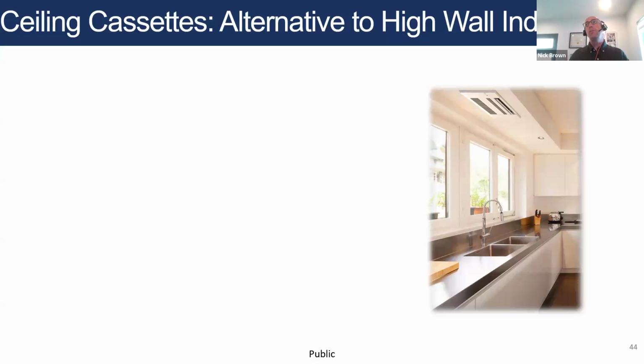Note that all these heat pumps are going to make condensate. So you need to locate the indoor unit, whether it's high wall or ceiling cassette or floor, somewhere where you can drain that condensate. So this kitchen location's ideal. Center of a room, sometimes not as ideal. And so you sometimes need to install condensate pumps when you don't have an easy path to drain the condensate water.